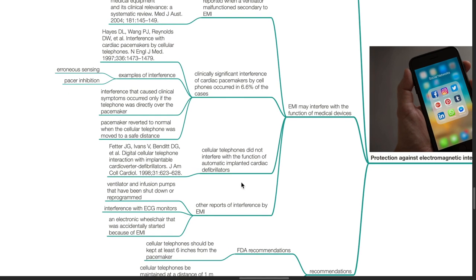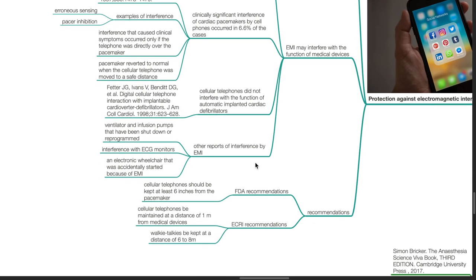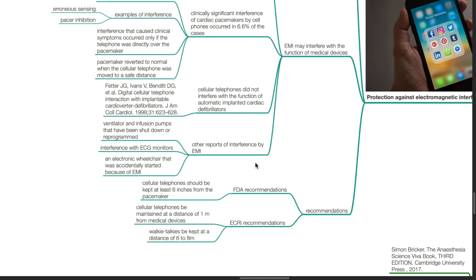In research done by Fetter et al, cellular telephones did not interfere with the function of automated implanted cardiac defibrillators. Other examples of interference by EMI reported include ventilators and infusion pumps that have shut down or reprogrammed, interference with ECG monitors, and electronic wheelchairs that were accidentally started due to EMI. FDA recommends that cellular telephones should be kept at least 6 inches from the pacemaker. ECRI recommendations include cellular telephones must be maintained at a distance of 1 meter from medical devices. Walkie-talkies be kept at a distance of 6 to 8 meters. These are my references. Thank you.